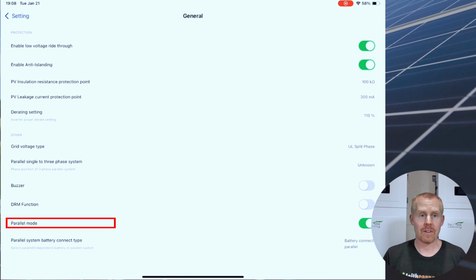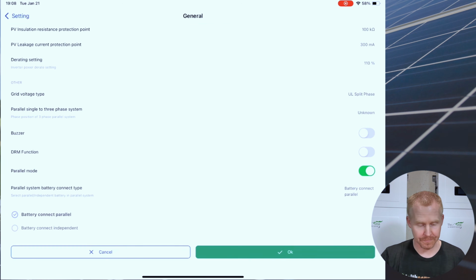Parallel mode, if you're having 2 inverters stacked and you're paralleling their outputs together, you need to enable this. And then parallel the system battery. Well, is each inverter sharing the same battery bank, or is each inverter using its own battery? I actually have not tried the battery connect independent. I don't know how it works. The 2 behind me are sharing the same battery bank. And so the primary inverter sends the state of charge and voltage information to that secondary inverter.